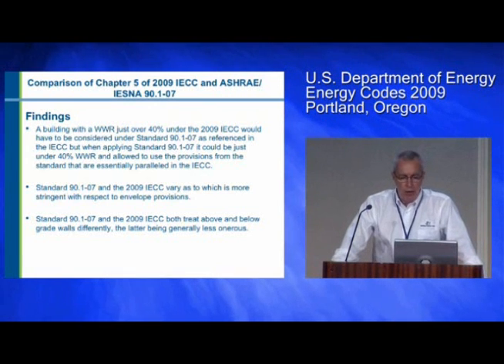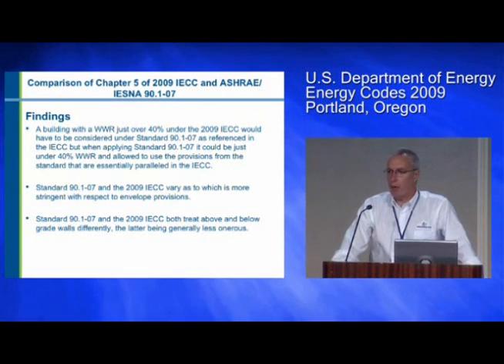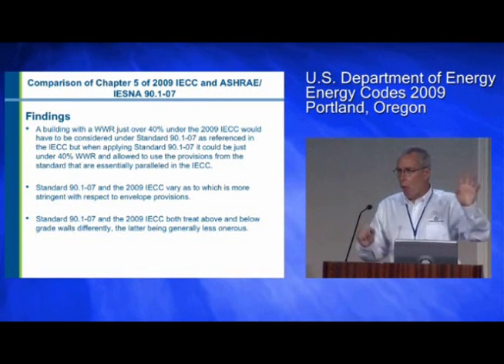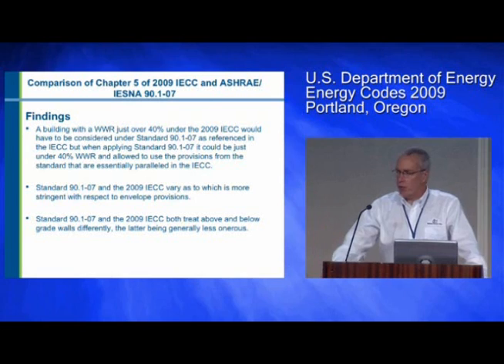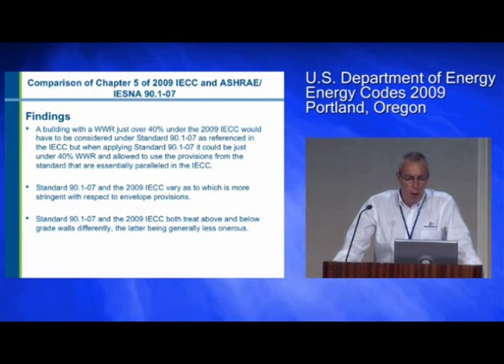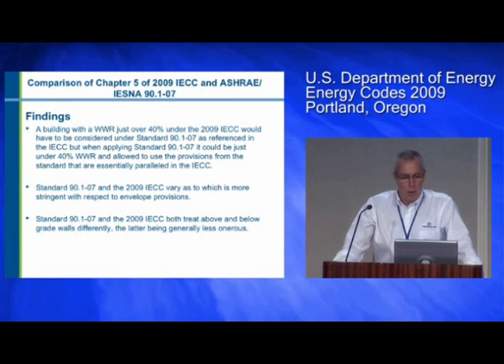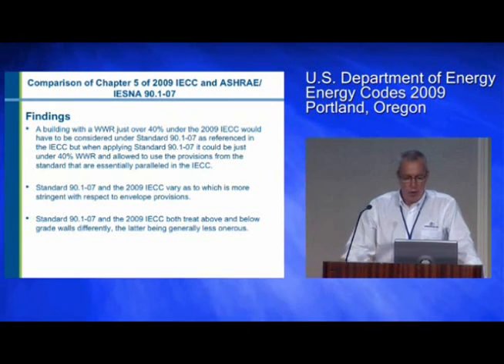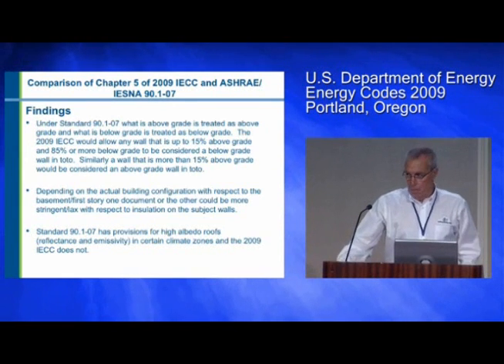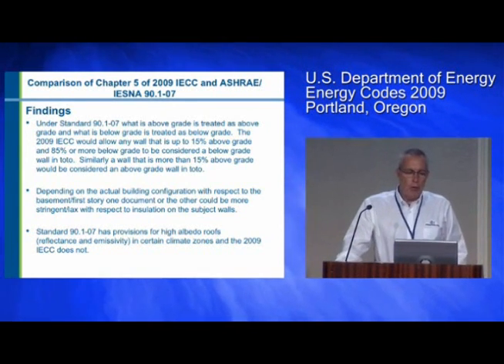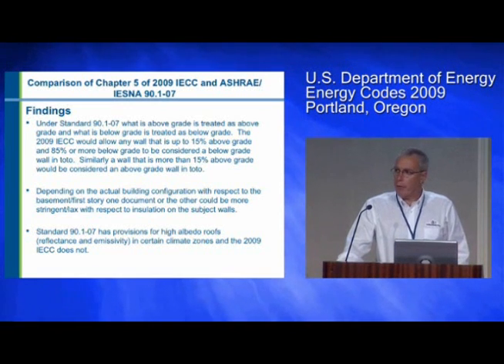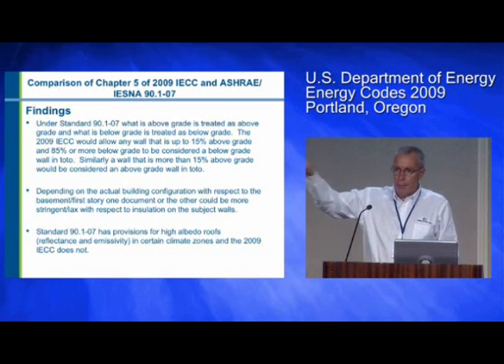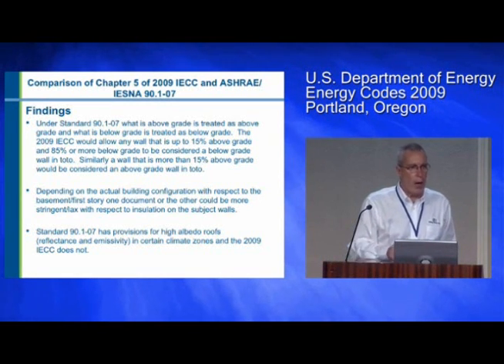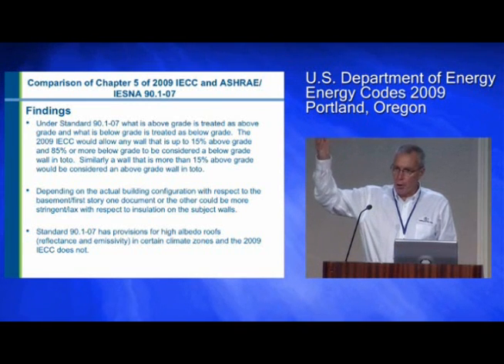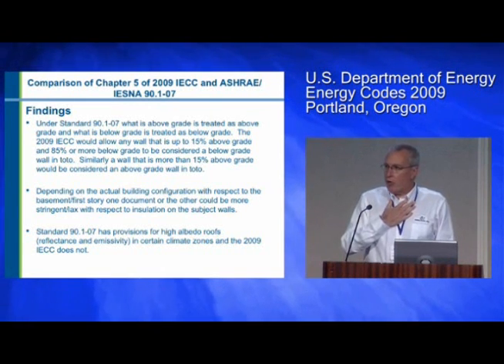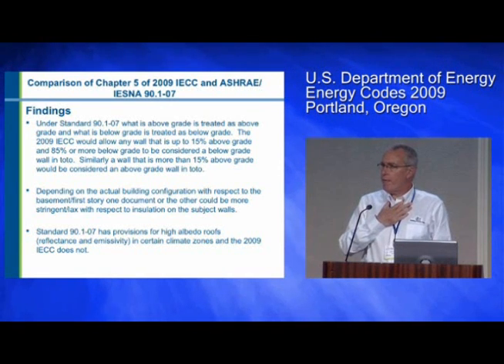So 90.1 and the IECC vary as to which is more stringent with respect to envelope provisions. When I take the fenestration, when I take the walls, et cetera, there are slight differences in the numbers. And the two documents treat above and below grade walls differently, the latter, the IECC, being a little bit less onerous. Under the ASHRAE standard, what's above grade is treated as above grade, and what's below grade is treated as below grade. Draw the line: anything below the dirt is below grade and meets one set of provisions; if it's above the dirt, it meets another. But in the IECC, I look at this 15%, 85% ratio.